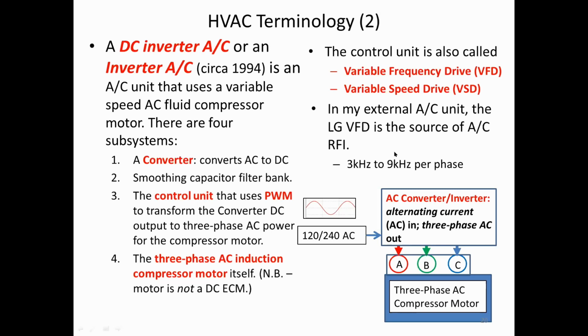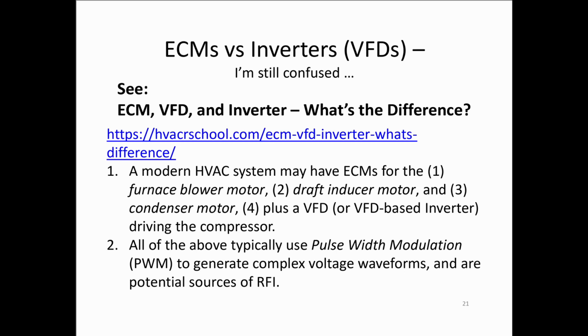Because just to repeat the last point, if you have an alternating current 3-phase motor, the only way to change the speed reliably and efficiently is to alter the frequency of the power applied to the motor to something other than 60 hertz. And that requires pulse width modulation to generate the appropriate waveforms. Now, at this point, you may be confused, but I hope people take away a simple message. ECMs are almost mandated in furnaces.